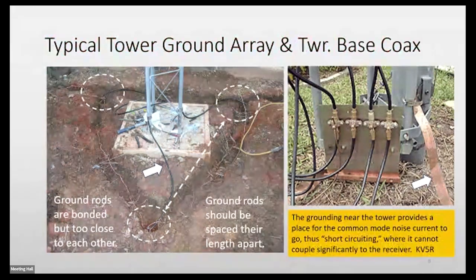Here's an interesting one, two slides - I'll talk about the one on the right first. The operator who put this in used bronze clamps, like the ones used for ground rods, clamped over the coax as it leaves the base of the tower. He's trying to get his coax at the same voltage potential as the base of the tower. This does two things: provides an equal potential of the coax to the tower, and creates an RF grounding scheme to reduce common mode currents and noise. Very effective - it's done in the commercial world all the time.